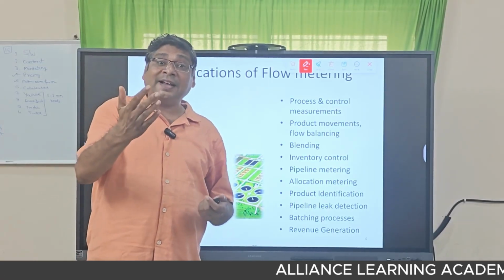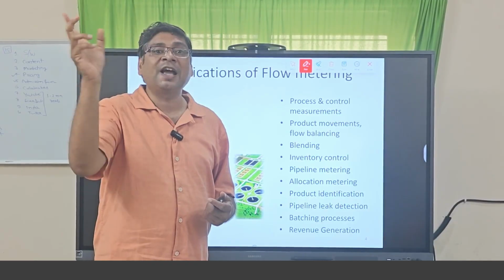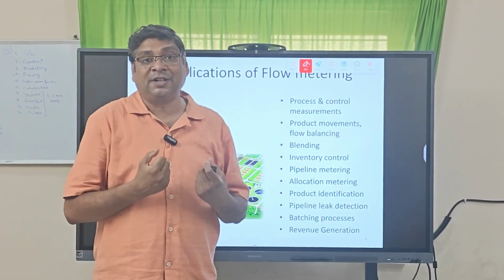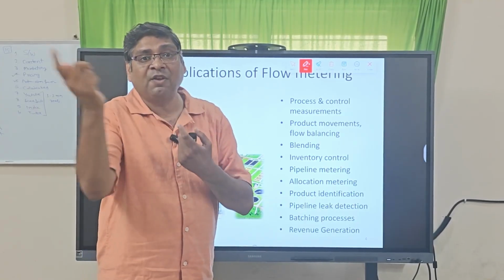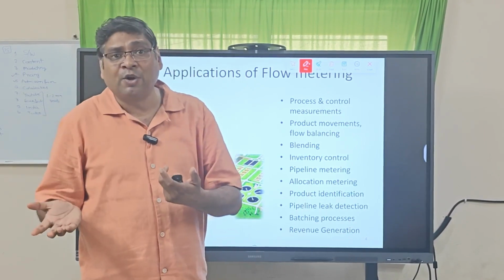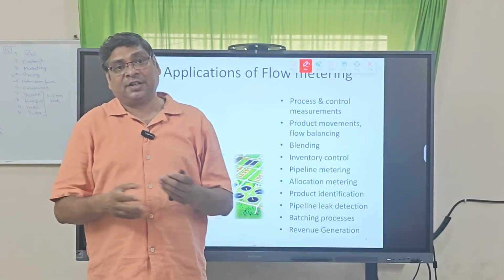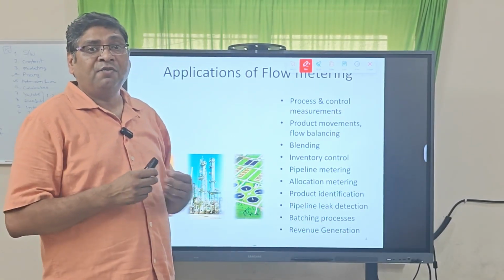Another example of this application is in a blast furnace. When making steel, in a blast furnace, there are tuyeres to cool down the shell of the furnace. There we use matched pair flow meters, and if the readings of the two flow meters at the inlet of the flow tuyeres and the outlet do not match, then we immediately switch on another tuyere to prevent overheating in the furnace. So this is a very interesting and very important application for flow measurement.